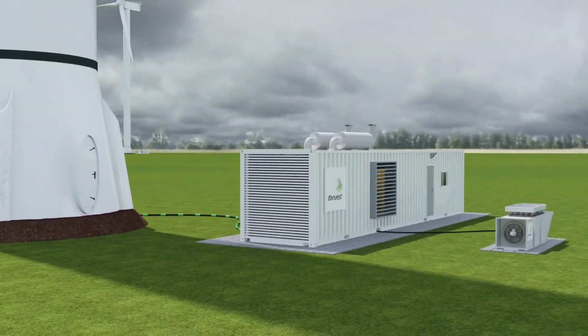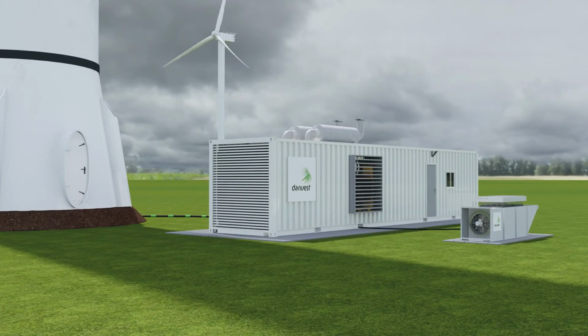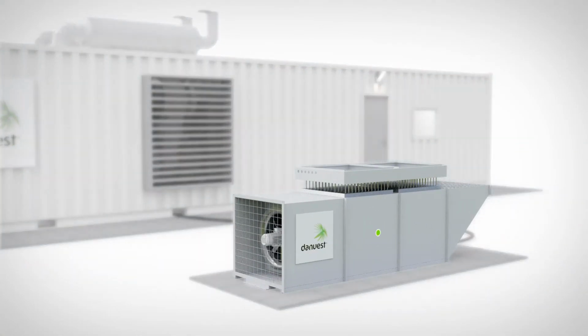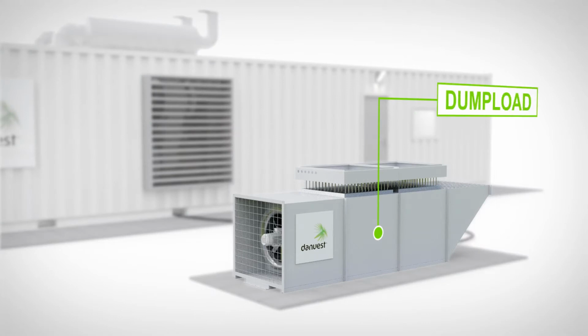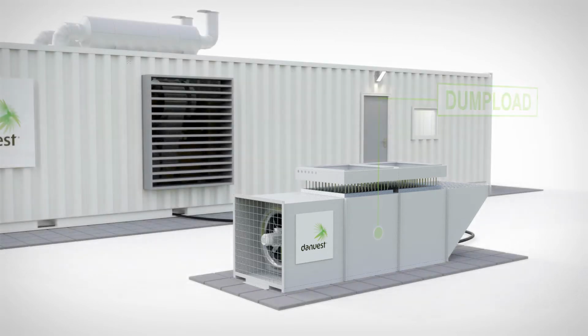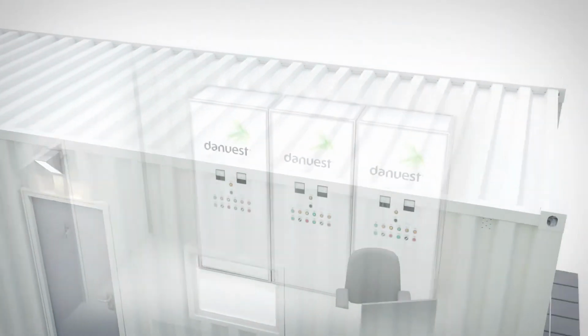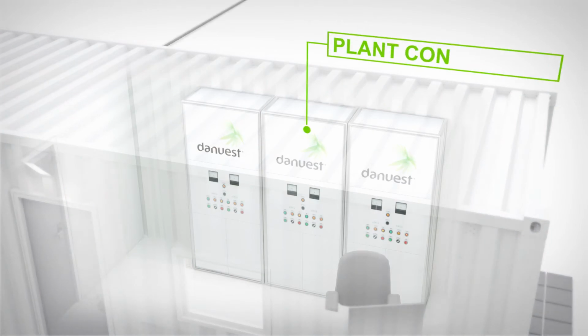Danvest is based on the reliability of diesel generators, and mainly diesel expertise is needed to operate a Danvest hybrid power plant. The dump load system controls the power balance during periods of surplus renewable energy and assists the genset during fast load variations. The plant controller consists of normal diesel engine controllers and a Danvest hybrid plant controller.